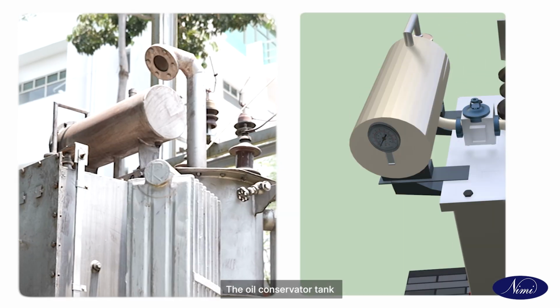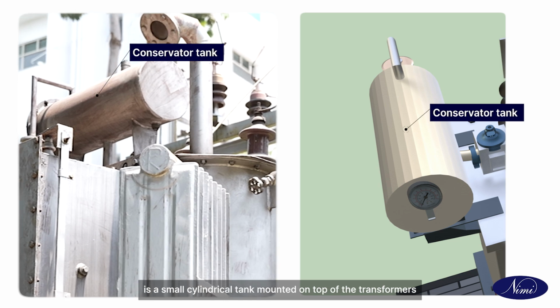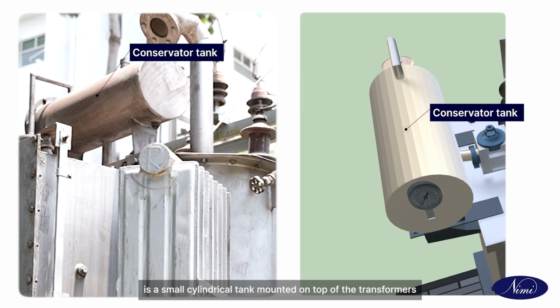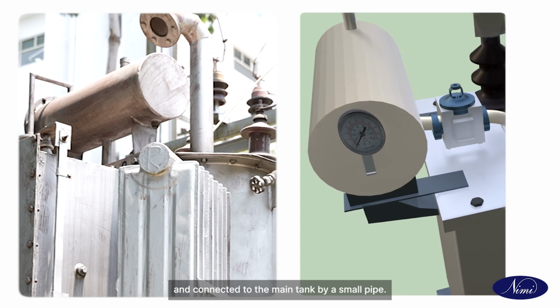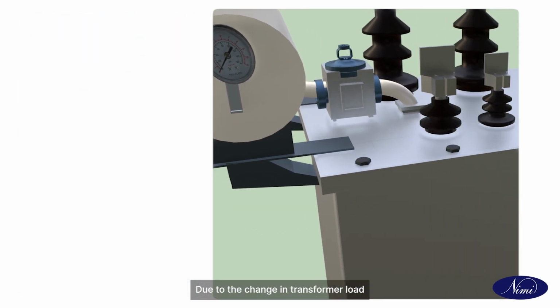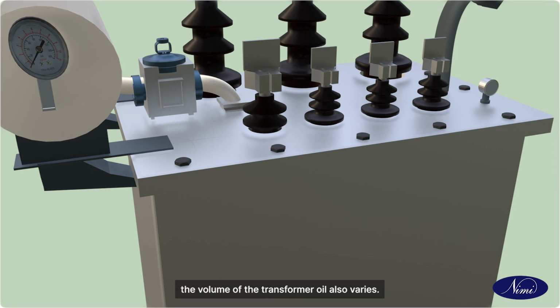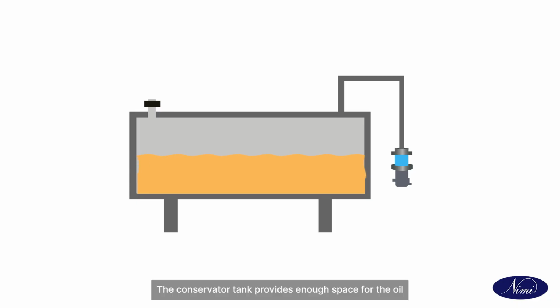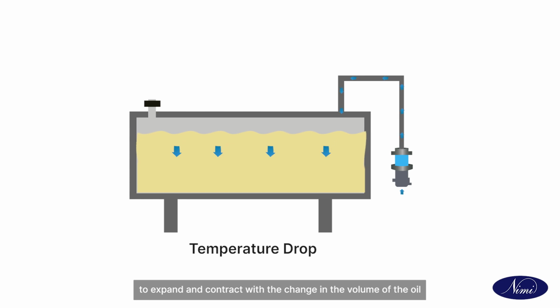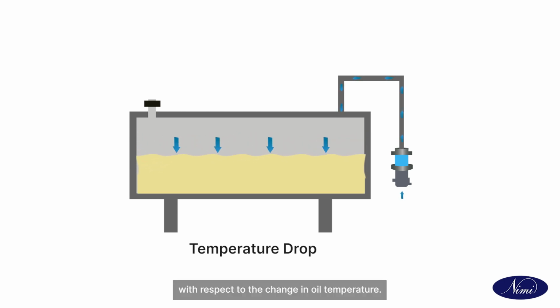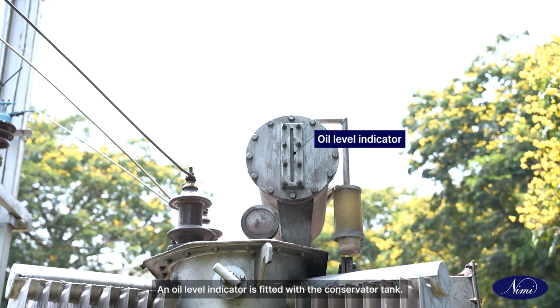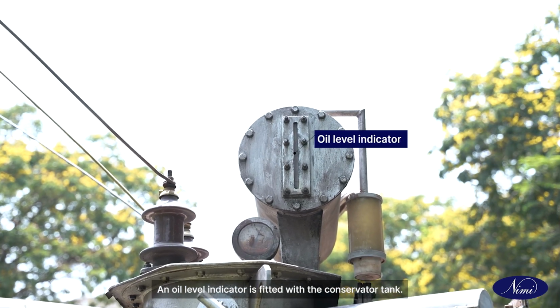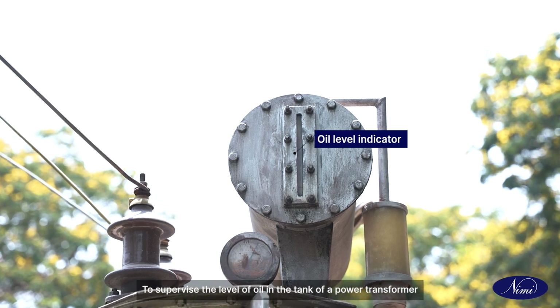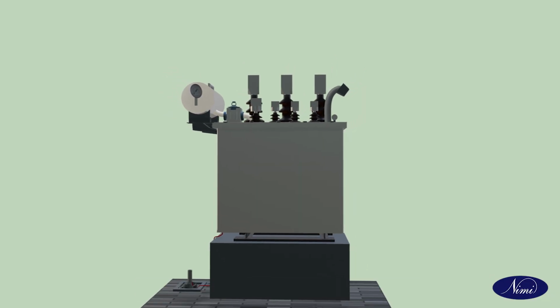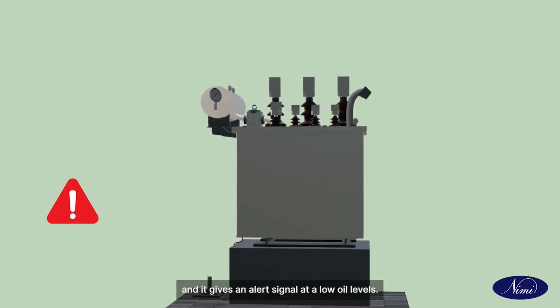The oil conservator tank is a small cylindrical tank mounted on top of the transformer and connected to the main tank by a small pipe. Due to the change in transformer load, the volume of the transformer oil also varies. The conservator tank provides enough space for the oil to expand and contract with the change in oil temperature. An oil level indicator is fitted with the conservator tank to supervise the level of oil in the tank of a power transformer, and it gives an alert signal at low oil levels.